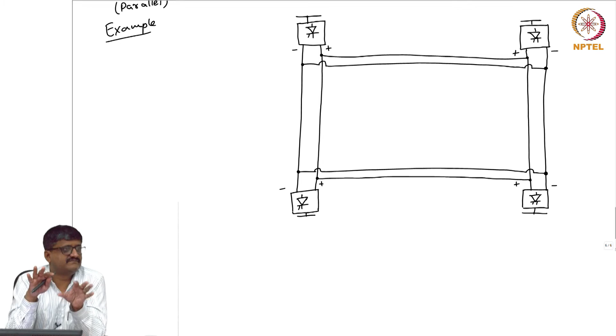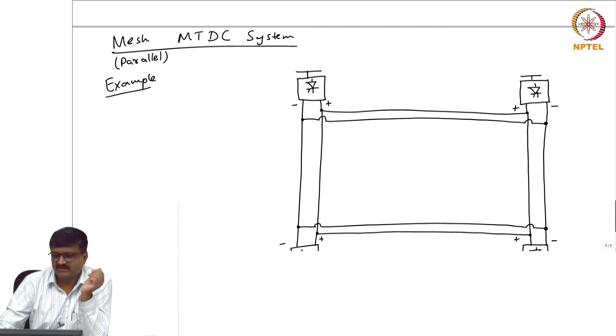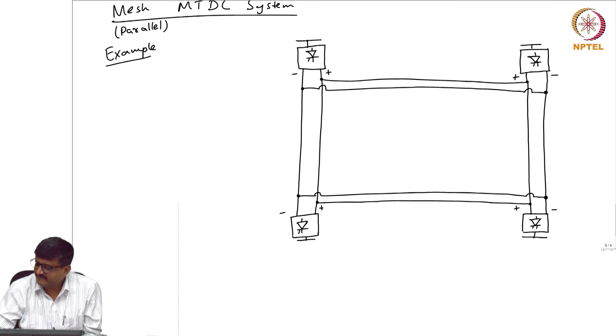Now, this is similar to the AC transmission system. Our AC transmission systems are mesh connections, unlike most of the distribution systems which are radial. If you have a radial connection, if you lose one feeder or one transmission line, then you will form islands. But in a mesh system, if you lose one transmission line, then the system is still interconnected. Okay, so that is the difference between radial and mesh. Now, mesh appears as if we have some redundant connections, but that is for the sake of reliability.